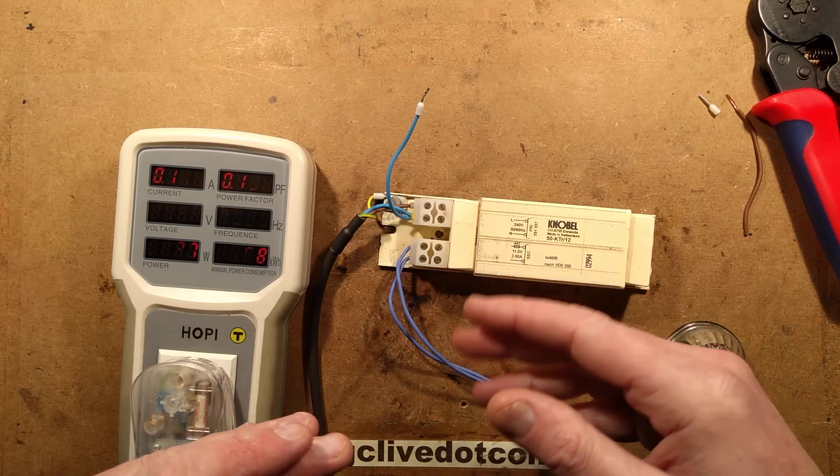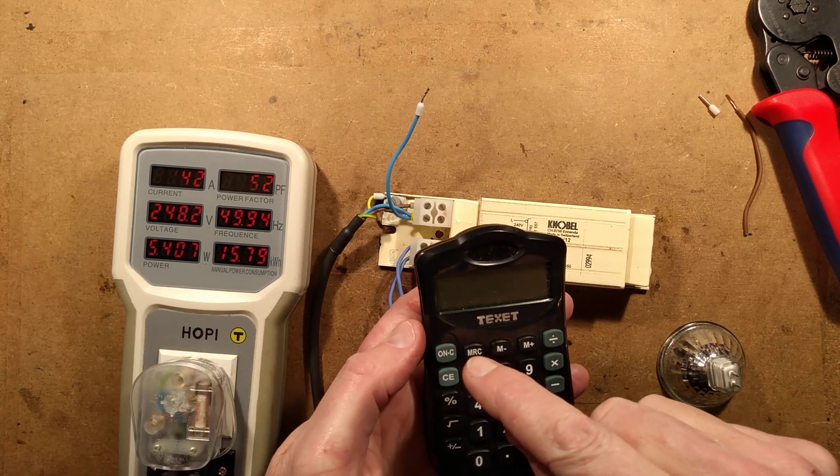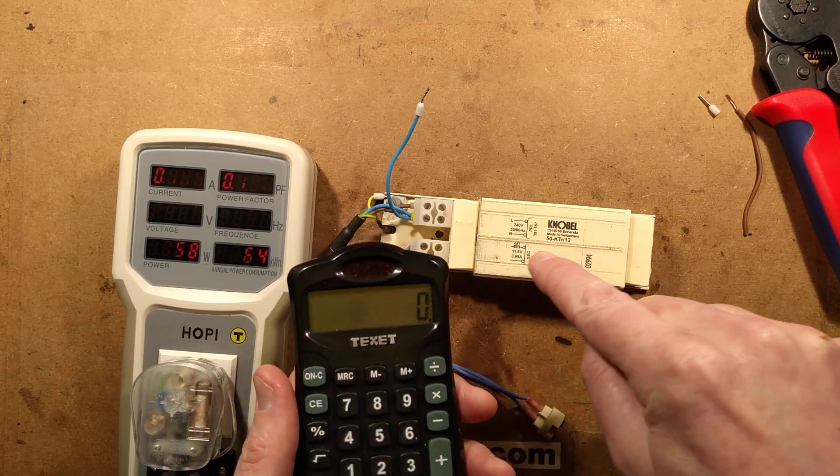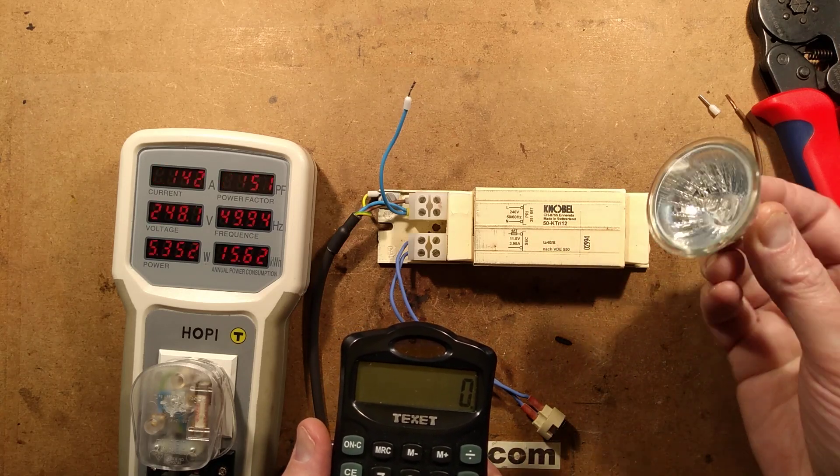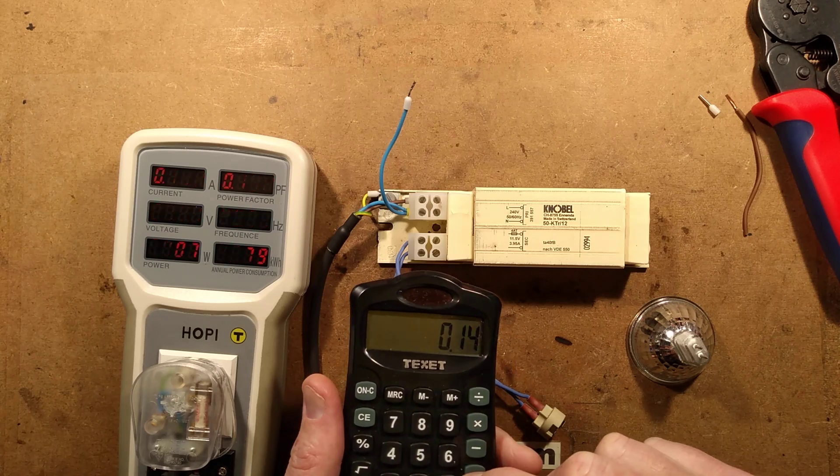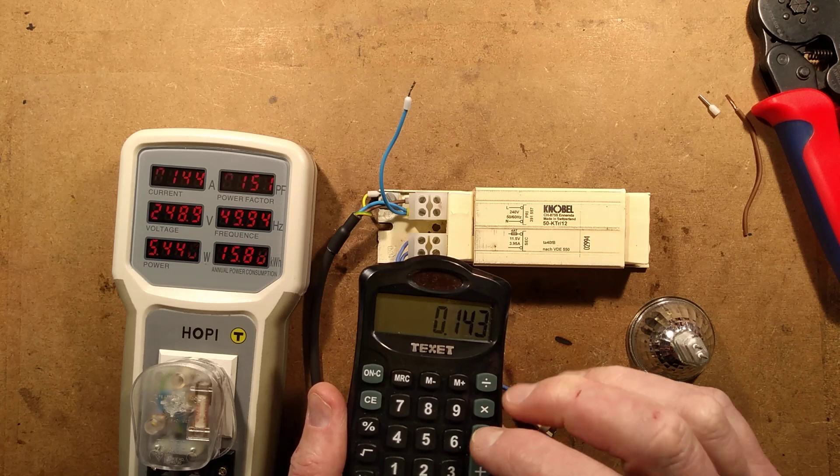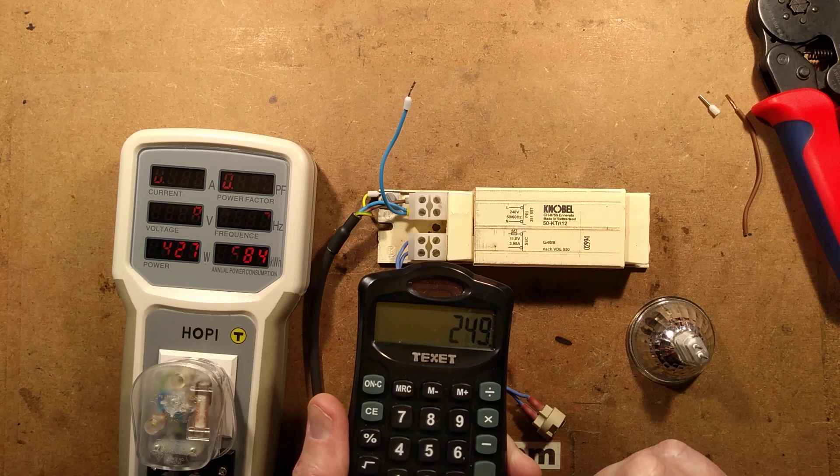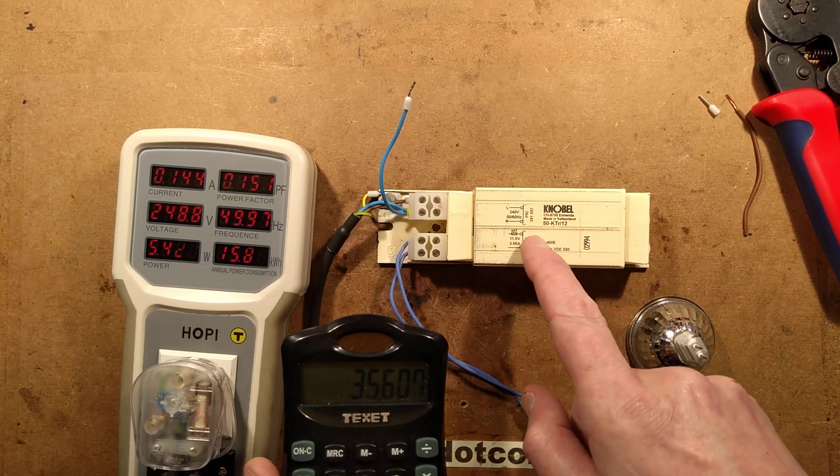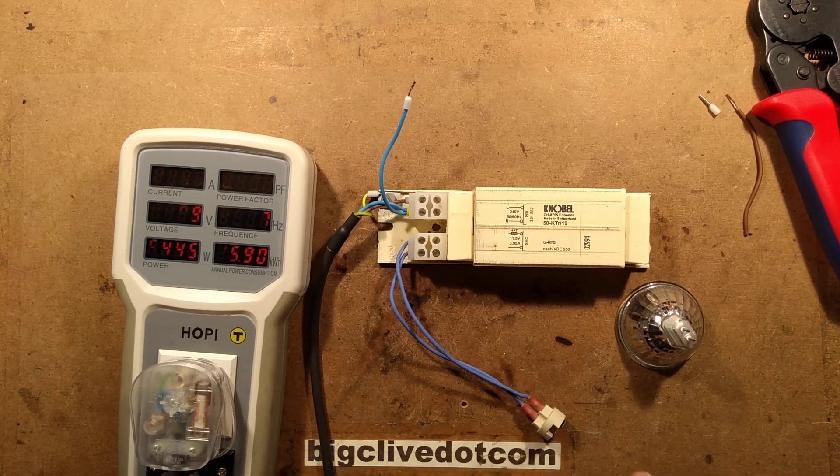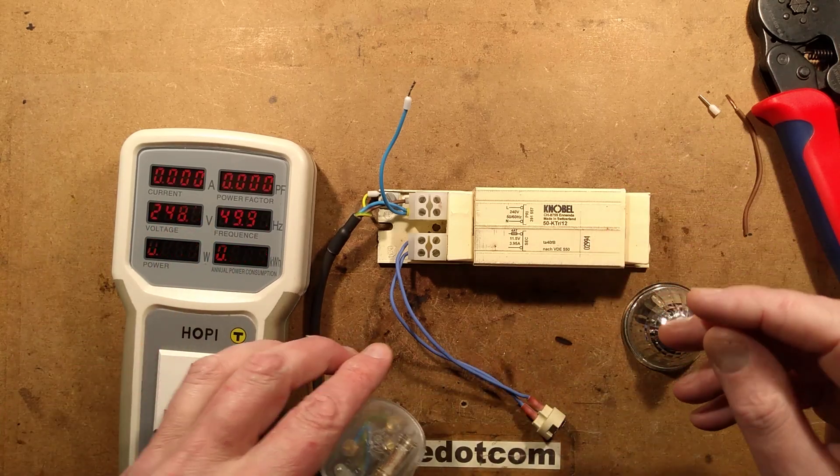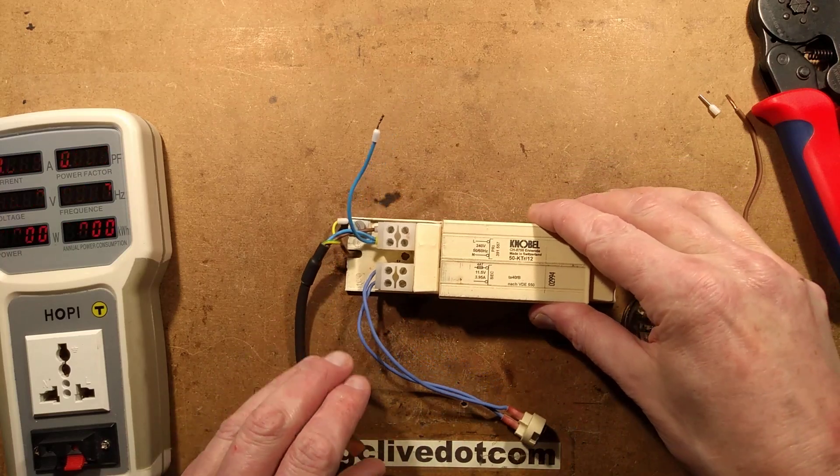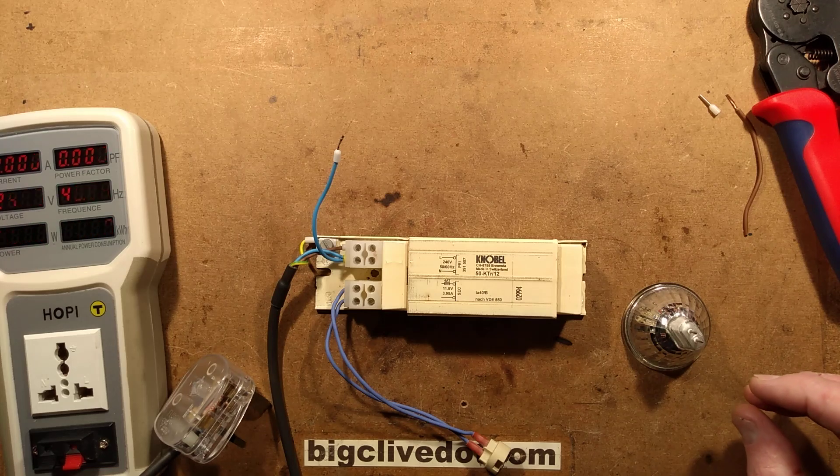Now, the power factor is a relationship between the voltage and current. Normally, it's not much of an issue. But if the power companies start charging for apparent power, then theoretically this ballast here, this transformer with the dead lamp in it, is going to cost 0.143 times 24, well actually it's almost 249 volts at the moment. Wow. This is going to cost the equivalent of a 35 watt lamp to run just with no lamp in it, if they start charging.